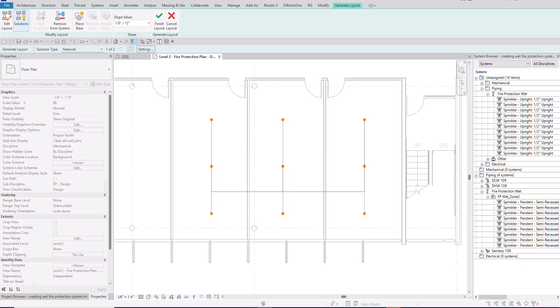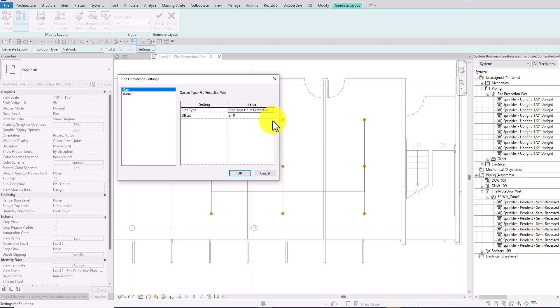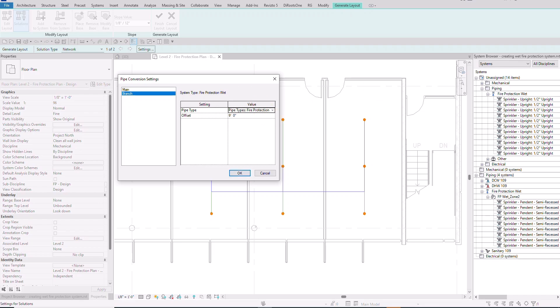I'll select Settings to check the pipe parameters. Under main pipe parameters I have the pipe type and offset. I'll make sure fire protection wet is selected — it already is — and the offset is nine feet, meaning the main pipe is placed nine feet above the current level, which is Level 2. For the branch pipe, the system type is also fire protection wet with the same nine-foot offset.